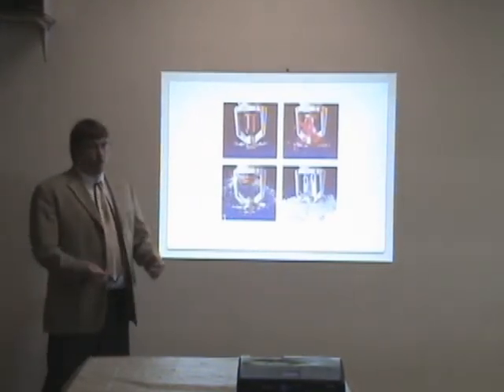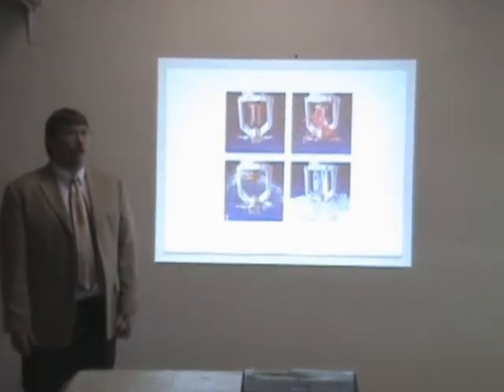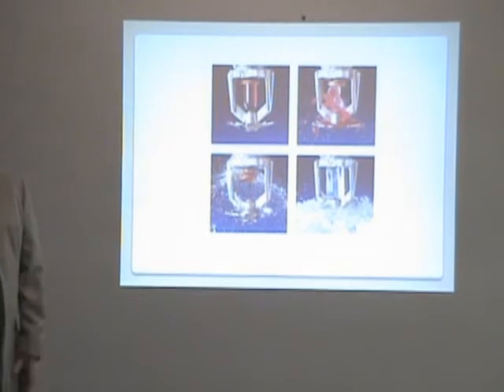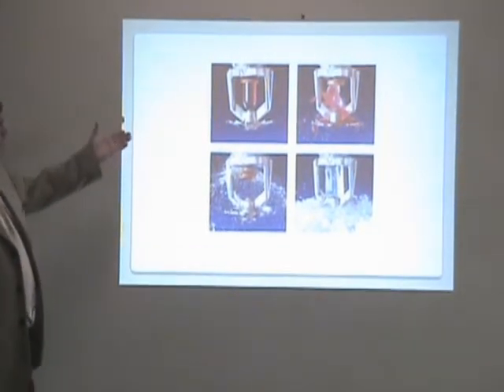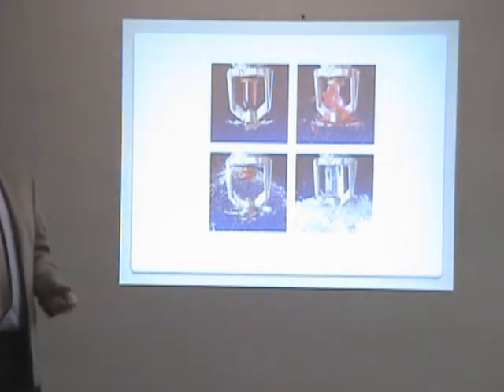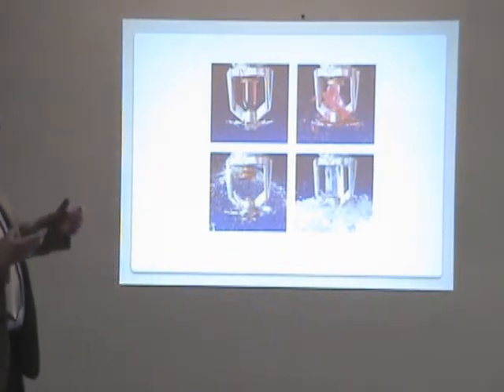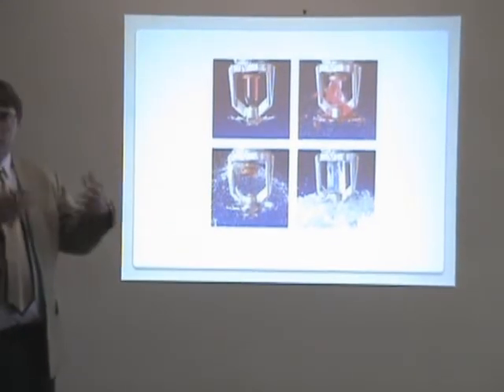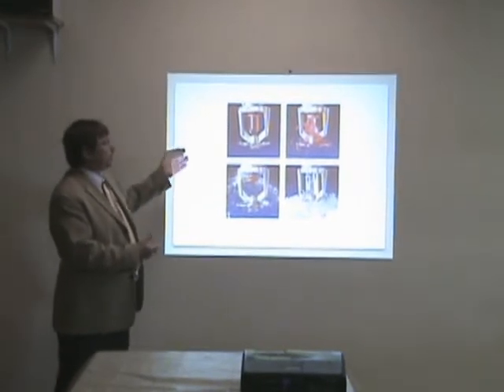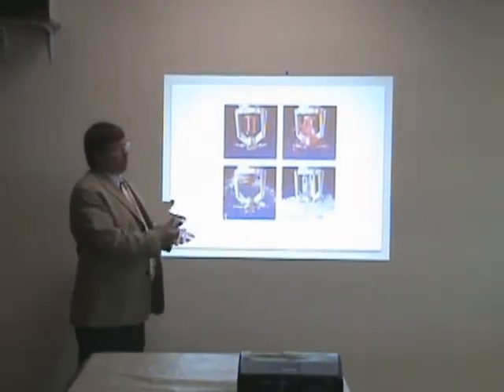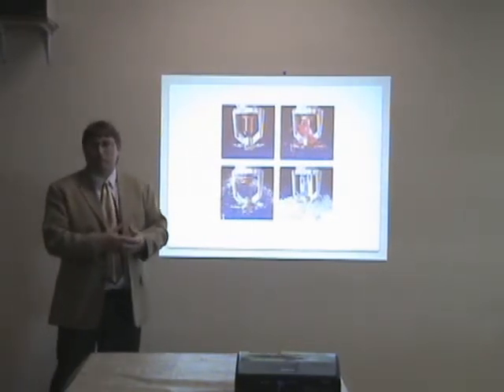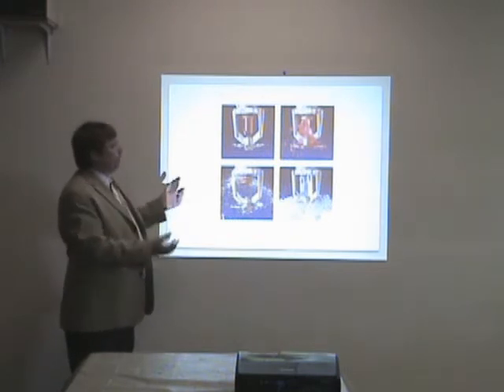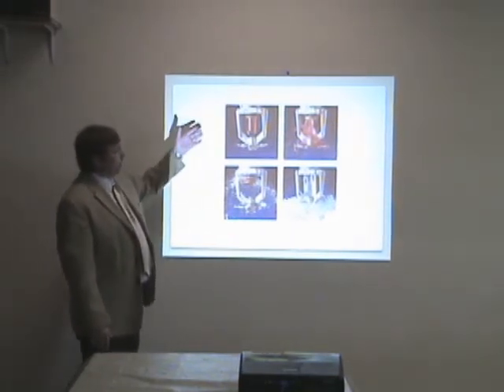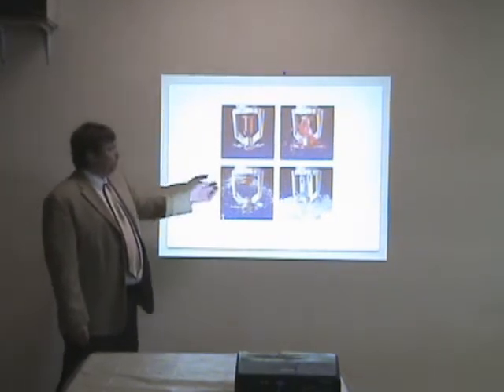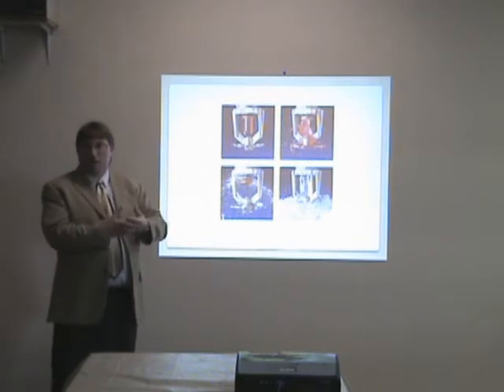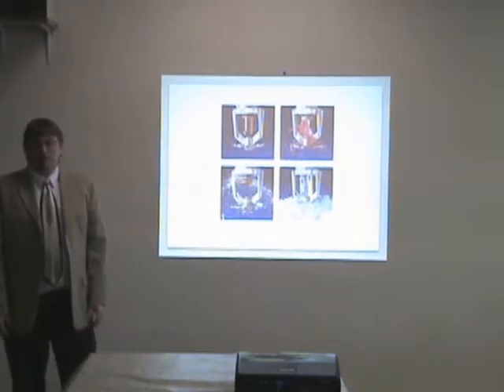Sprinkler heads are what's termed closed heads. They are closed in that the water is kept from spraying out of the head by a heat responsive element. In the example here, you'll see the red cylinder, and that's a liquid filled cylinder that is set at a certain temperature that will melt out and let the sprinkler head open at a particular temperature, in this case around 155 degrees. When the sprinkler head reaches that temperature and the heat responsive element begins to respond to that heat, the element will melt out or break, as you see in the picture at the top right. At that point, there's a seal that drops out, the water pressure pushes that seal out, and the water begins spraying out of the sprinkler head.